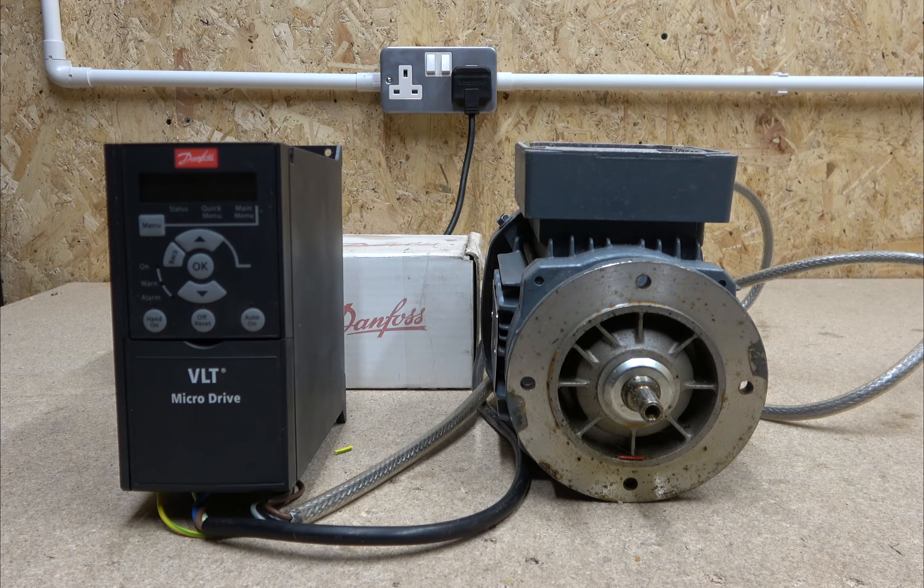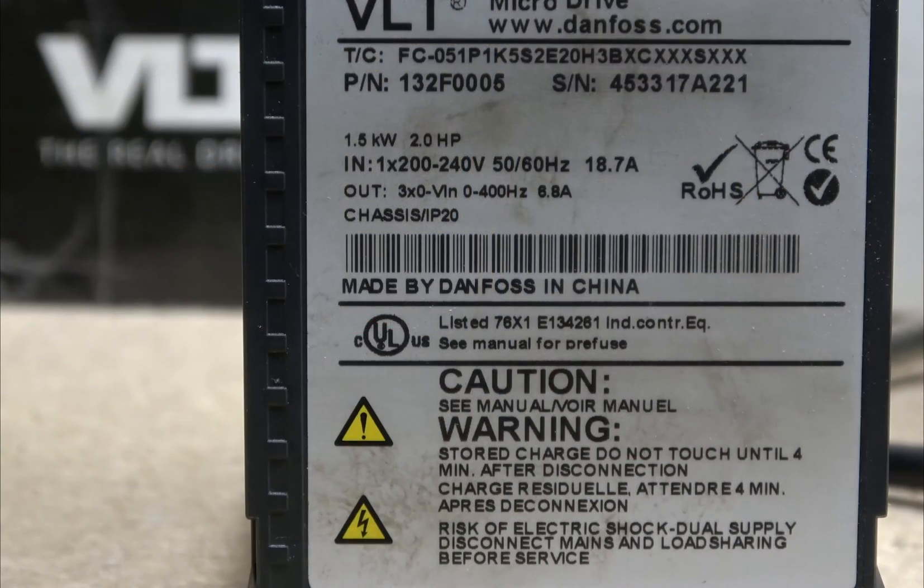First, we need to identify what sort of cables we need to wire this drive into the power source. Let's have a look at the label. It says we're going to be running this drive at 1.5 kilowatt, 2 horsepower, with a 200-240 volt supply requiring 18 amps. So I would put that on a 20-amp separate fuse with a 4mm cable, depending on your distance.